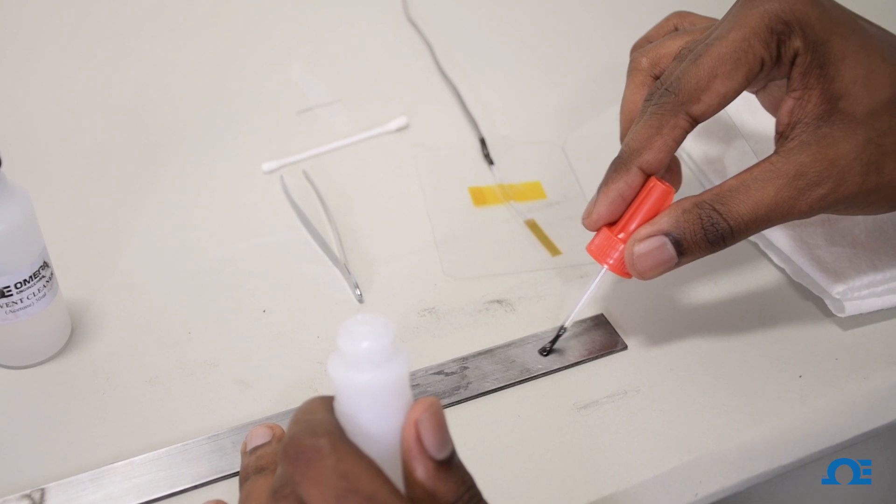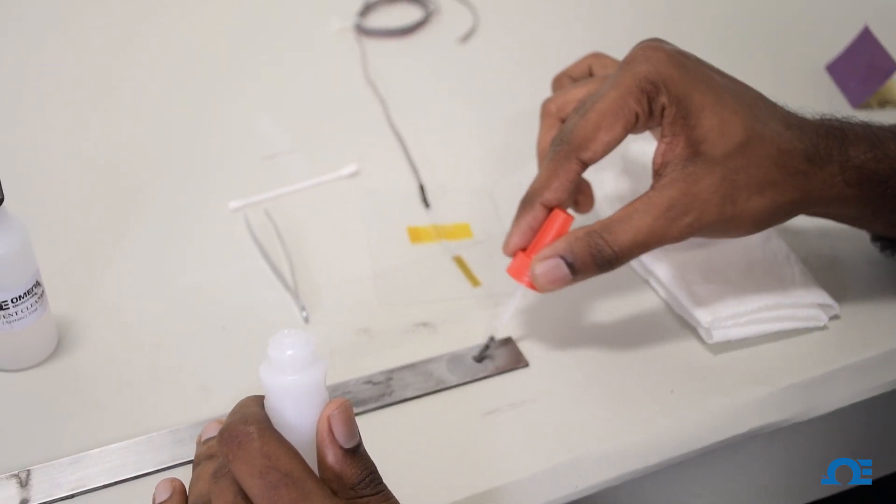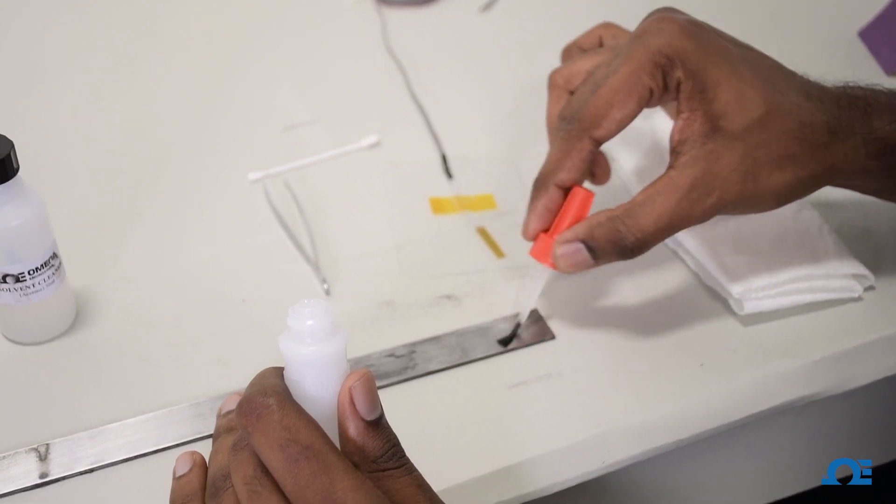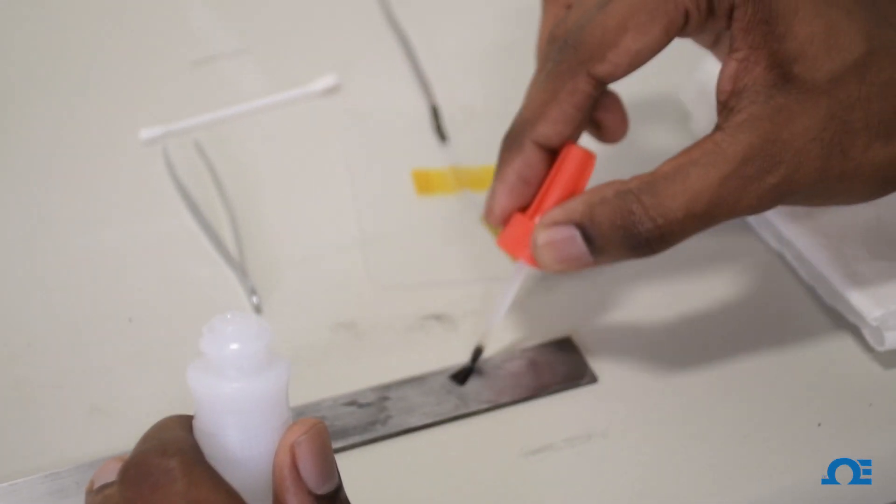And then apply a few drops of the SG496 adhesive, or you can use any cyanoacrylate based adhesive instant cure, on the surface where you want to apply the strain gauge. Apply a uniform coat.